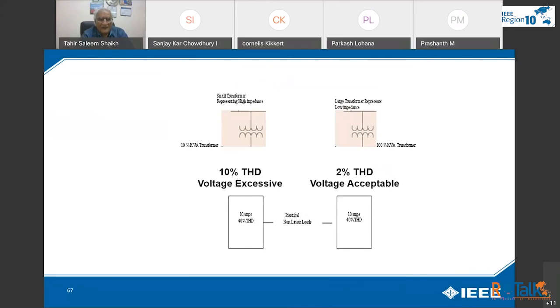Now, one solution for this is to increase the size of your power equipment. So in this case, there is a transformer which gives you 10% THD voltage. If you increase the size, it will reduce to 2%. And generally, it is a general practice that you should not increase the non-linear load on a transformer or a generator to more than 20%.